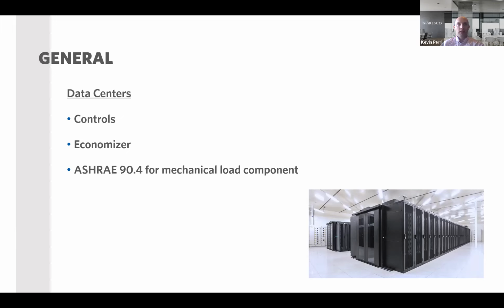So data centers do have to follow the ASHRAE 90.4 section for mechanical load components. And really that's for the power required for cooling, fans, pumps, heat rejection, things like that. So data centers go to ASHRAE 90.4 to see how those are supposed to be designed now for the IECC portion of the code. So IECC is referencing ASHRAE.